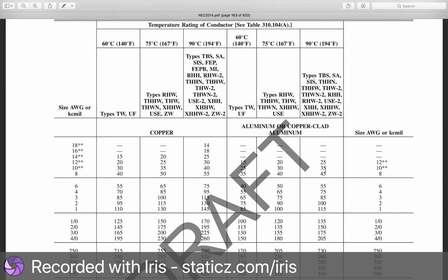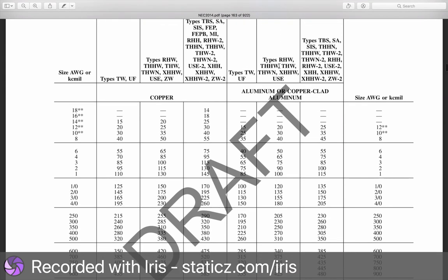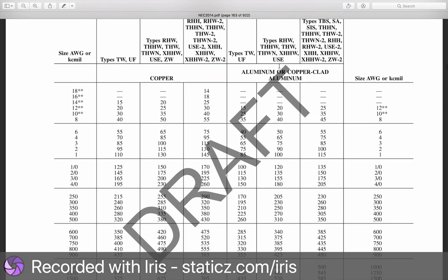More often, for the conductors you use and size out, you're going to use the 90-degree column. And sometimes, for certain reasons, we'll use the 75 as well, if our lugs are only rated for that, which we'll get into at another time.